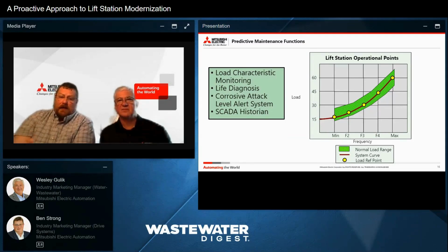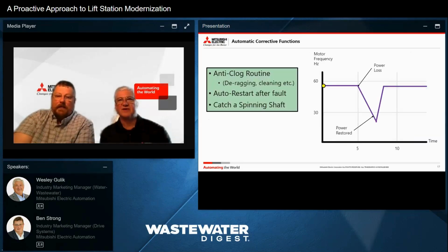On the other part, if I have high load at low speeds and it trends all the way up, I may have a bearing starting to fail. I may have a fouled impeller. There's other things that we can infer based on monitoring this. This is in most people's drives as a standard feature, but you have to turn it on. So something to think about. Key point, right? Turning it on.